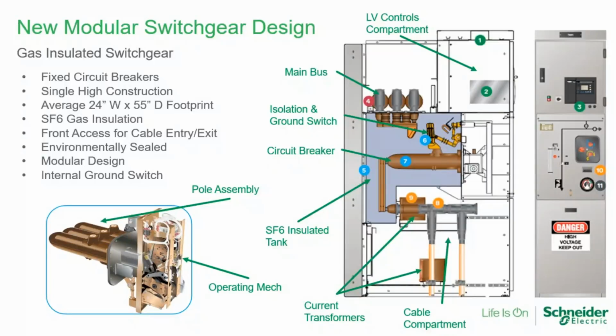Are breakers gas insulated as well in a gas insulated switchgear? So with gas insulated switchgear, you often have both options. And for those that aren't so familiar, I like to distinguish between the insulating medium, which is the gas, and the interrupting medium, that would be the bottle. So within the bottle of the circuit breaker, you can interrupt in a vacuum circuit breaker bottle and still be SF6 style insulated switchgear. Or often you have the option for an SF6 style interrupting bottle in SF6 style insulated switchgear. So it's important to distinguish between those two different types, whether it's the insulating material or the interrupting material. So really good question there.